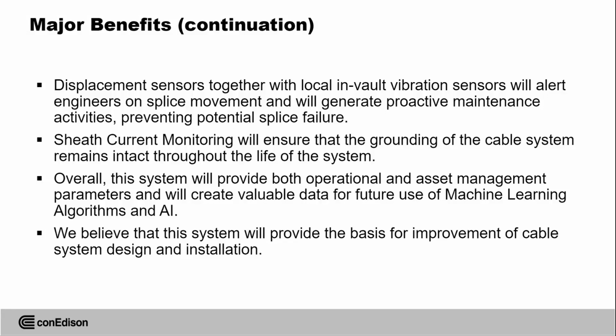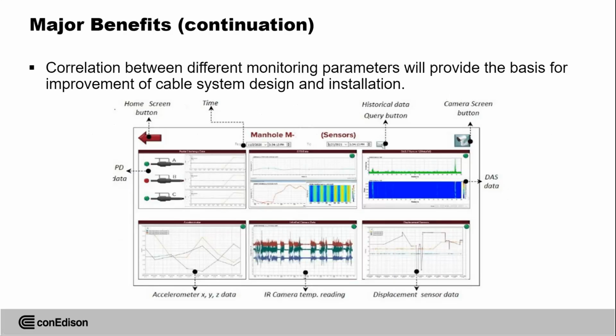But most important, we see that AI and machine learning algorithms can help us to correlate between different parameters. For example, how increased vibration strain can affect partial discharge, how a temperature increase can affect partial discharge, or how increased shield current can affect the cable performance and other parameters. So that's a major benefit, correlation between different monitoring parameters, and that will provide the basis for improvement of cable system design, installation and maintenance techniques.